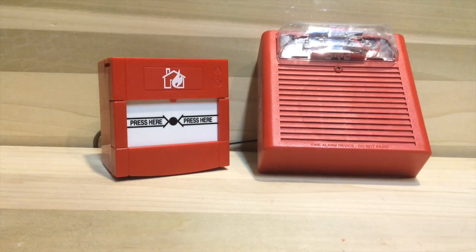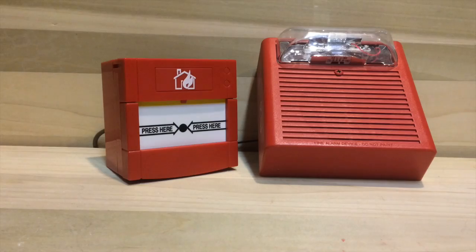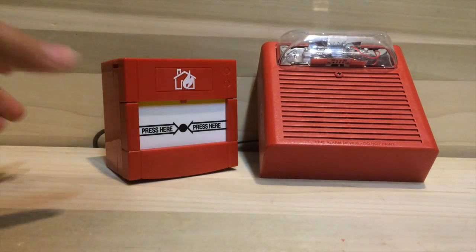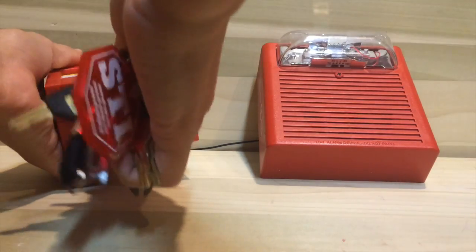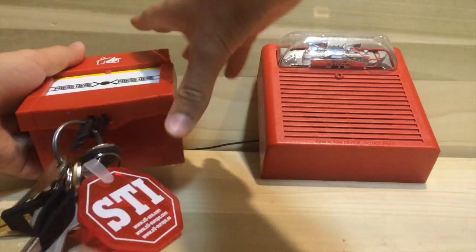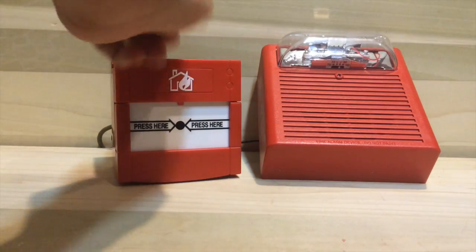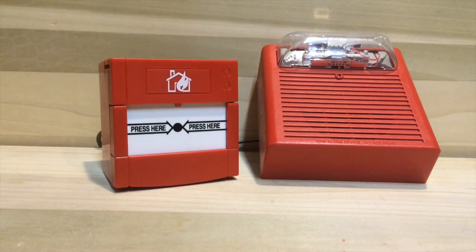While I have this all set up, I went ahead and turned on the horn. This thing is on code three low volume and still on 30 candela. We're now going to set it off — ready in three, two, one. These things can be a pain to reset sometimes, but they're pretty nice. I like call points a lot.